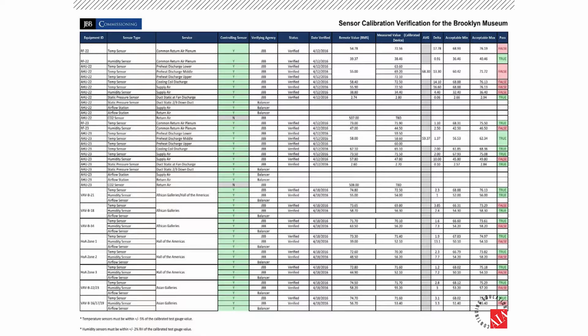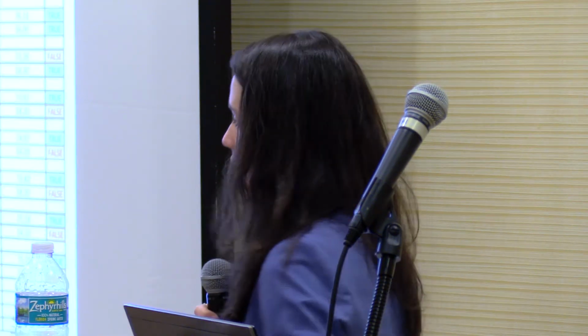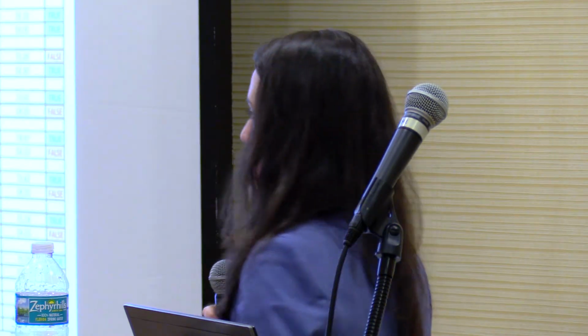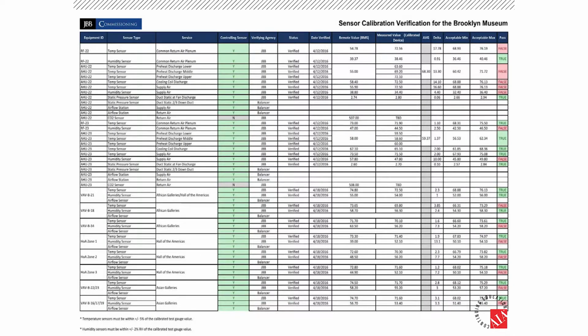Here's some of the documentation that we used during the sensor accuracy verification. There's a lot of information on this, but really what's important are the colors, right? On the right-hand side, that's a pass or fail in terms of calibration. There's a lot of red there, right? There were a lot of things that failed. In fact, I think it was close to 37% at the end of the day. Controlling sensors in this facility were out of range or out of calibration, right? So some important takeaways there that definitely helped us explain some of the issues moving forward.